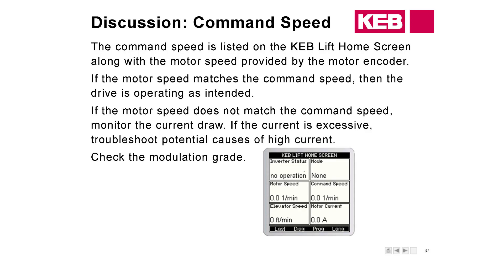A couple of other things we can look at. Number one: command speed. Are we actually getting a speed from the controller? Sometimes you go to run and you're not going to move, and in this case we're not drawing any current either — we don't have a command speed. On the home screen you'll be able to tell; command speed would just remain at zero.